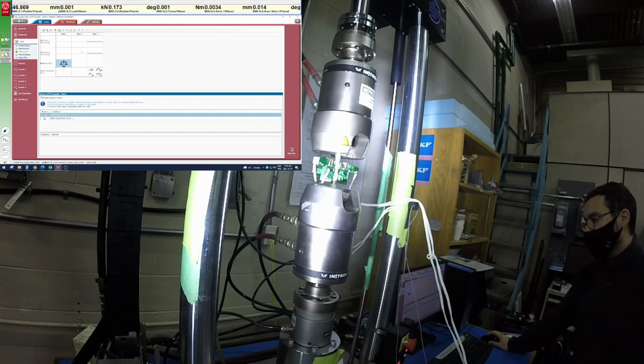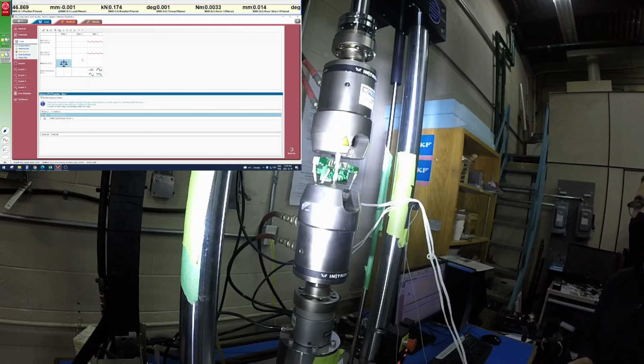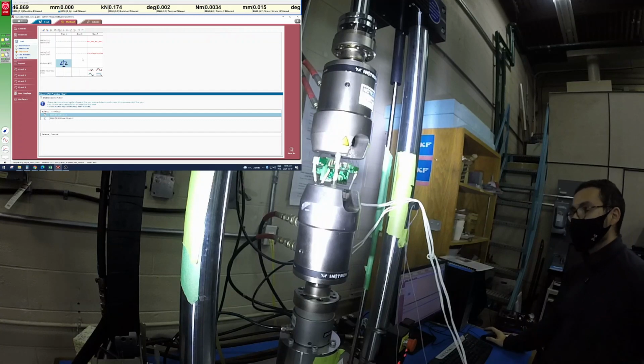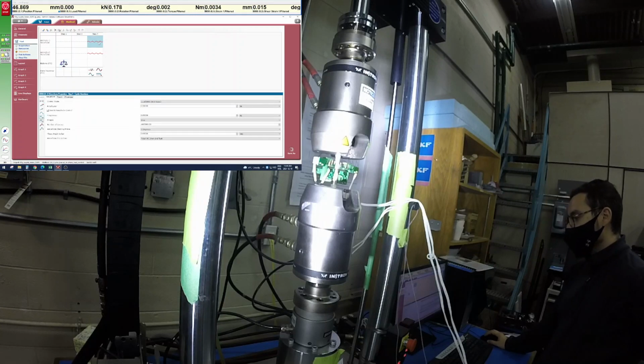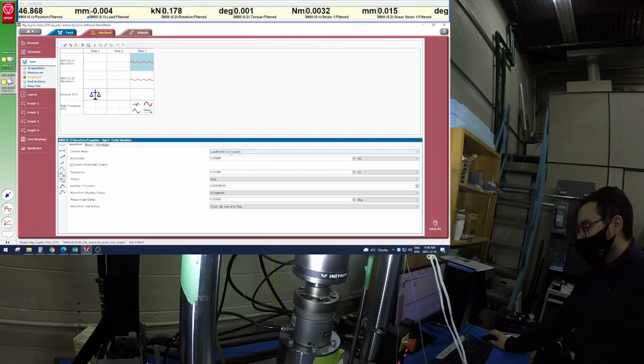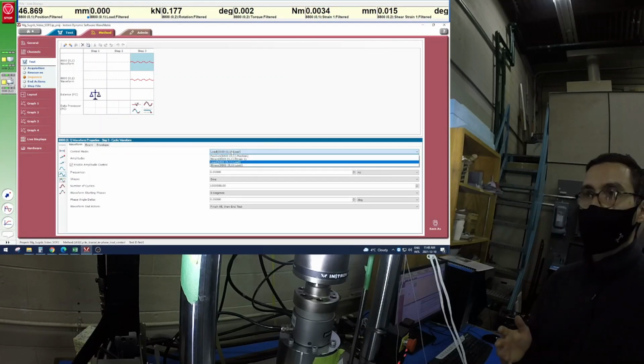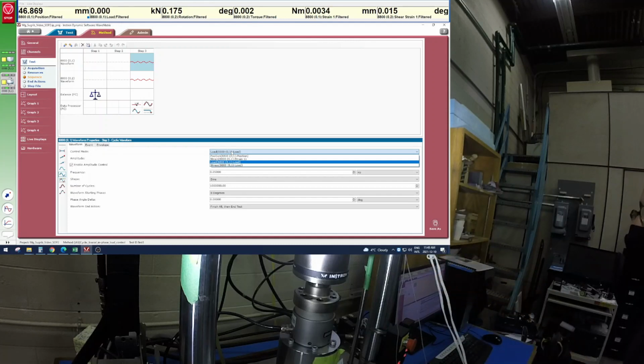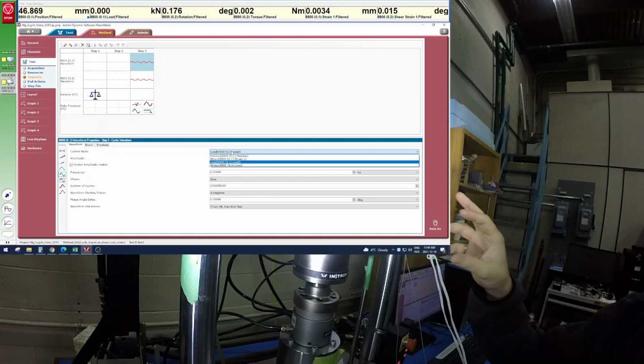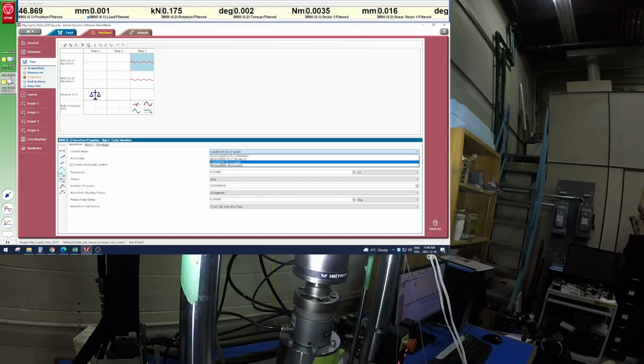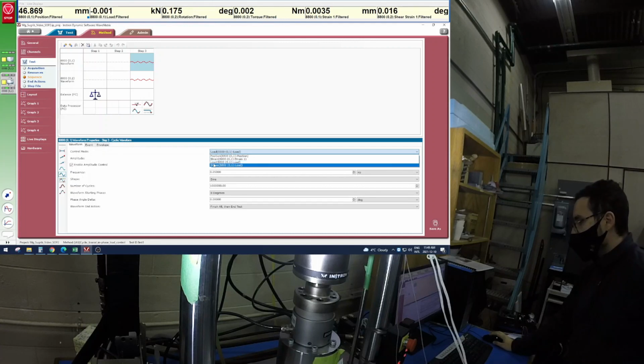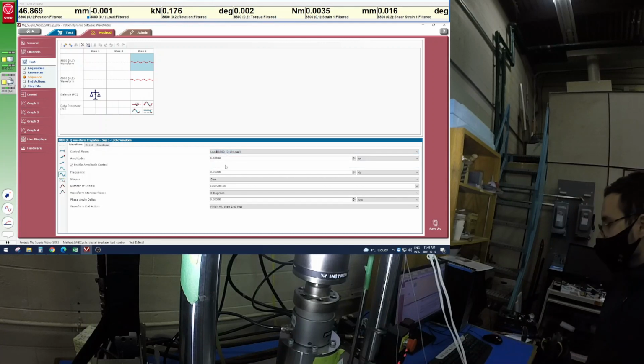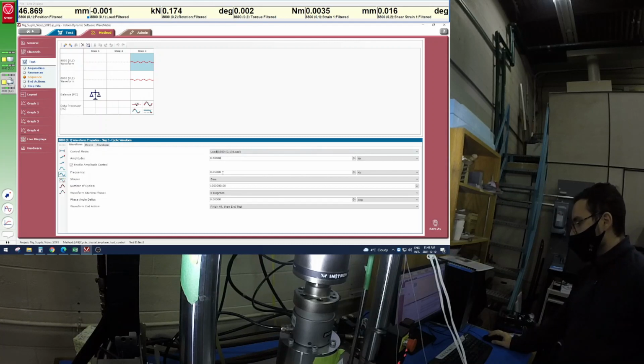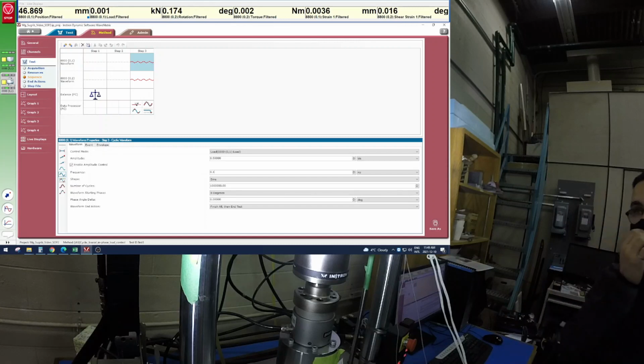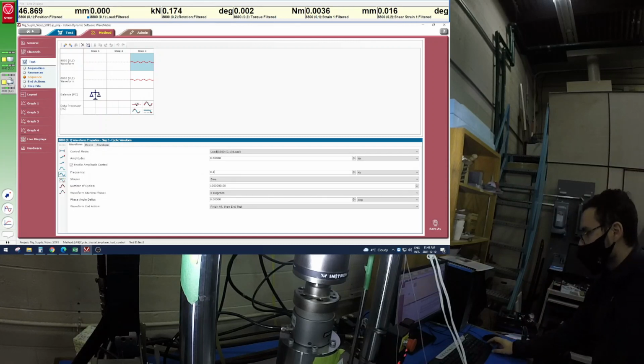Then there's going to be a hold in between. These are 2 things that are pretty much going to apply to all different procedures. The things that you really change here are the waveforms that you're going to be subjecting the sample to. So the first waveform at the top right here is your axial waveform. So we're applying the control mode of load. We're not going to do a strain control test here. We're going to do a load control test and measure the strain, just for purposes of trying to do it as quickly as possible so you can see the hysteresis loops develop. So we want to do a load control test here, and we are going to do an amplitude of 500 newtons, and we are going to do a frequency here of, let's say, 0.1. So that's going to be 10 seconds to complete a full cycle. We can click enter.